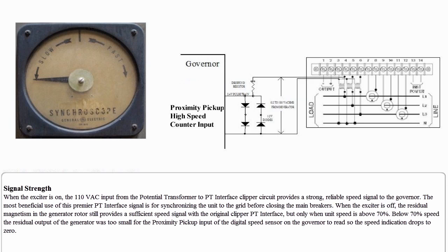The most beneficial use of this premier PT interface signal is for synchronizing the unit to the grid before closing the main breakers. When the exciter is off, the residual magnetism in the generator rotor still provides a sufficient speed signal with the original clipper PT interface, but only when unit speed is above 70%. Below 70% speed, the residual output of the generator was too small for the proximity pickup input of the digital speed sensor on the governor to read, so the speed indication drops to 0.